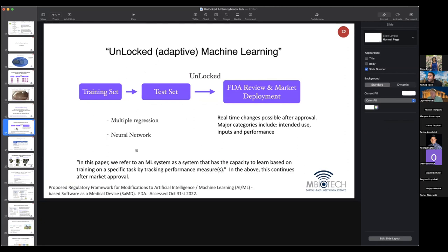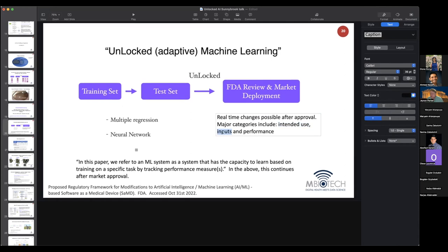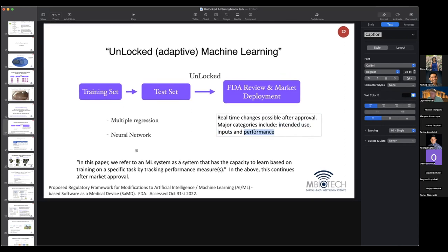An unlocked neural network would have a training set or test set as before, but now it's unlocked. When put on the market, it can continue to learn. We're talking about real-time changes in the neural network that can change its clinical decision-making. Over time, it could change its intended use, the kinds of patients it's prepared to deal with, the kinds of inputs it's working with, and its performance may change. These are major areas of uncertainty for something released on the market that will change.